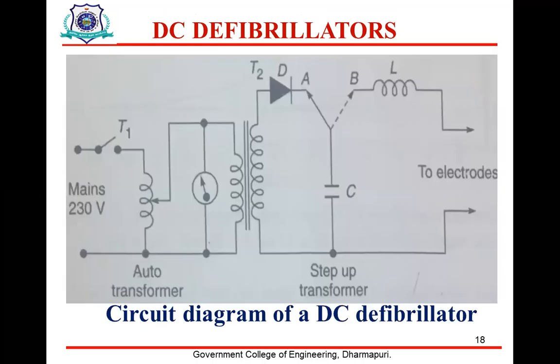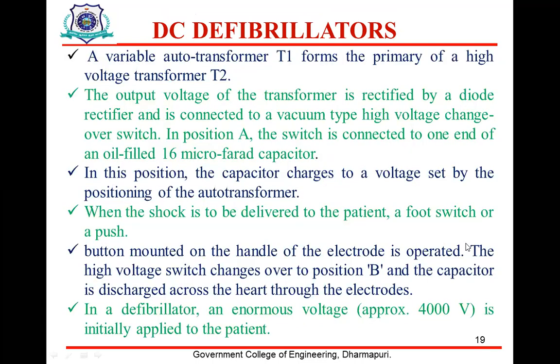So this is the circuit diagram for a DC defibrillator. There is an AC mains supply, an auto transformer, and then a step-up transformer. The output will be given to the electrodes. In the diagram, a variable auto transformer T1 forms the primary, with a high voltage secondary. The voltage output of the transformer is rectified by a diode, which acts as a rectifier, and it is connected to a vacuum type high voltage changeover switch. At position A, the switch is connected to one end of the oil filled 16 microfarad capacitor. In this position, the capacitor charges to a voltage set by the position of the auto transformer.